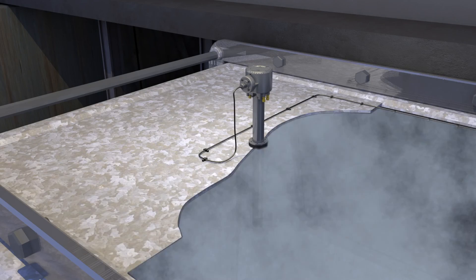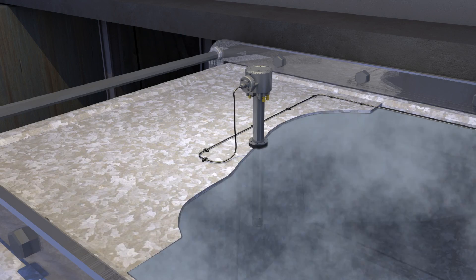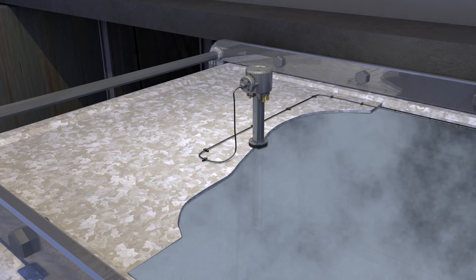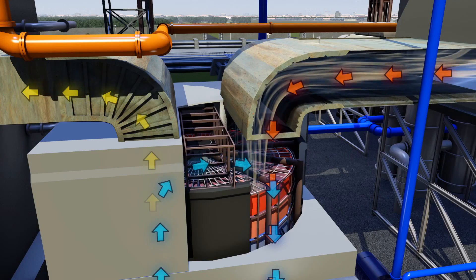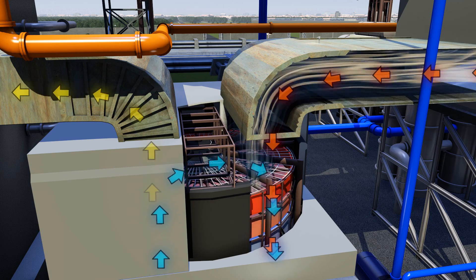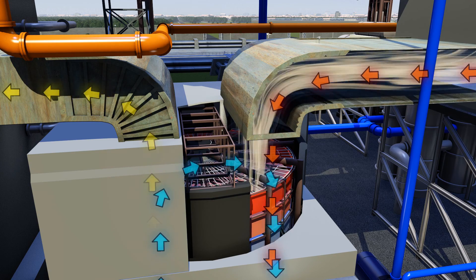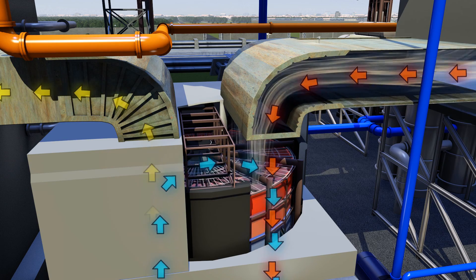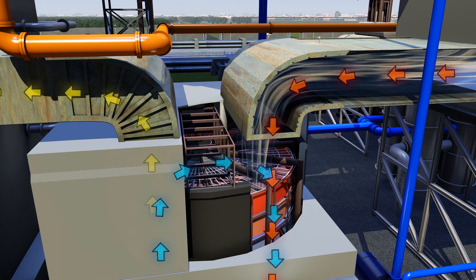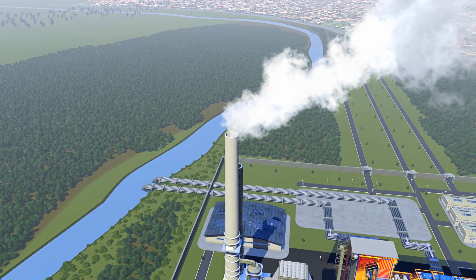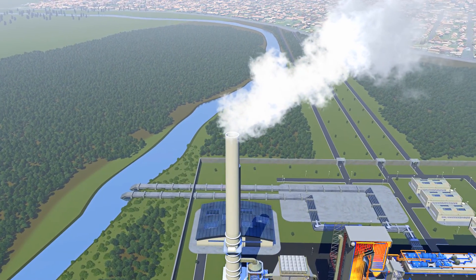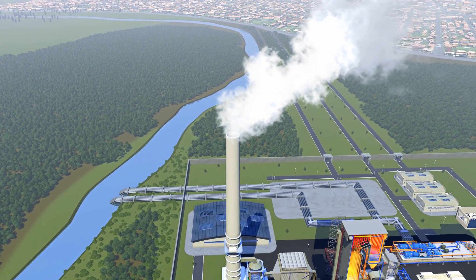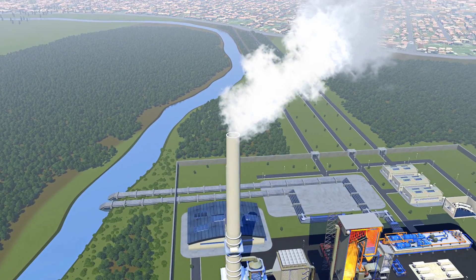Higher readings detected by the probe on the exit will indicate seal wear, as combustion air leaks into the flue gas. By monitoring data from the probes, a maintenance schedule can be created to check and replace worn seals.